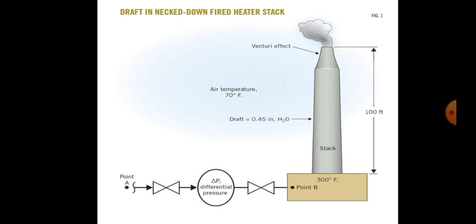So like this, if the temperature has to go down, then the heat has to be used more effectively. So the stack temperature should be as low as possible. However, it should not be so low that water vapor in the exhaust condenses on the stack walls. So it should have some temperature, but not as low as possible. A stack temperature greater than 200 degrees centigrade indicates the potential for recovery of waste heat.